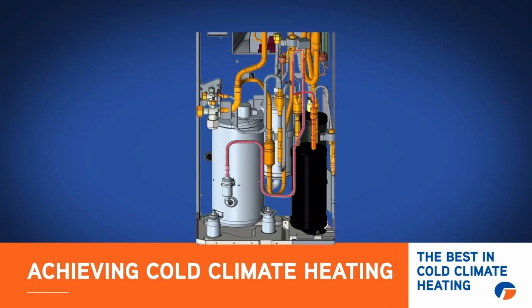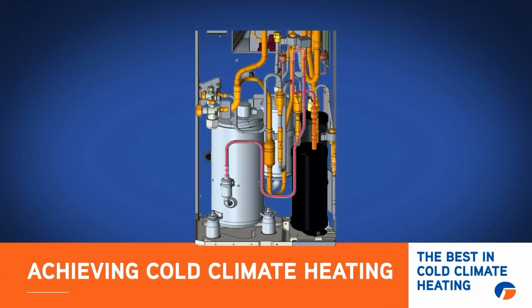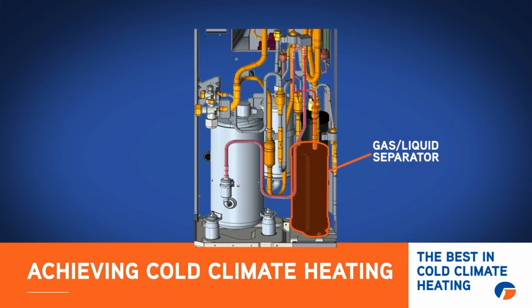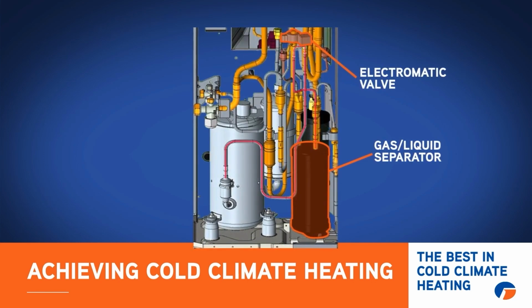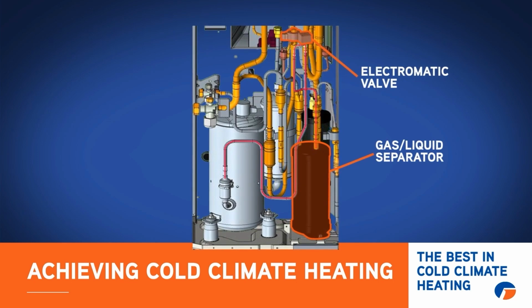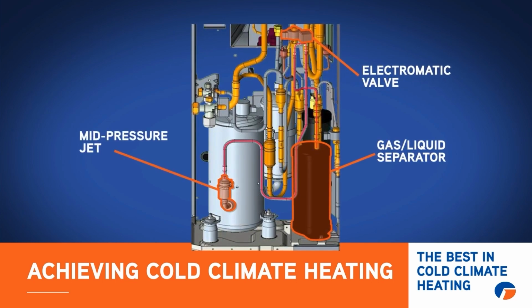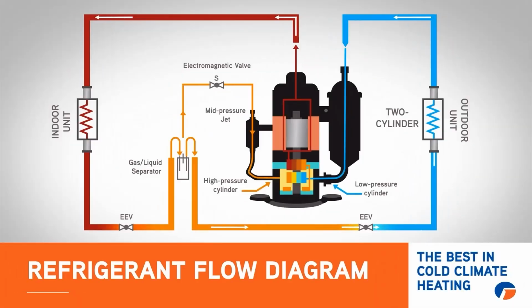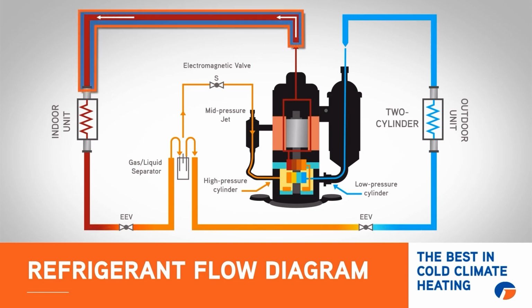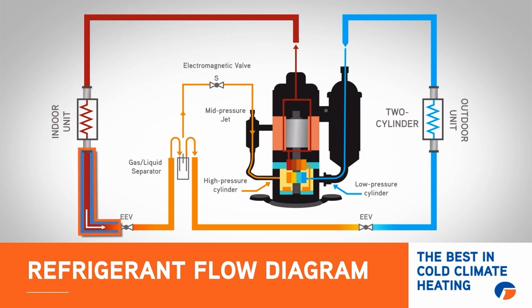For the ultra heat compressor to achieve cold climate heating, the following components are needed: a gas liquid separator and the electromatic valve. With those 2 components, refrigerant can flow through the electromatic valve into the mid-pressure jet of the compressor. Let me show you how this all works together. Here's the refrigerant flow diagram of the Flex unit with the ultra heat compressor. Normal refrigerant flow in heating mode: hot gas refrigerant is discharged off the top of the compressor to the indoor coil, where heat is released into the indoor air. The refrigerant condenses back into a liquid and then flows to the secondary EEV.